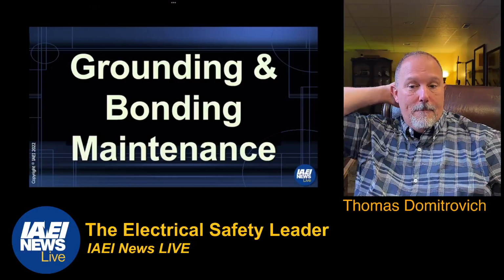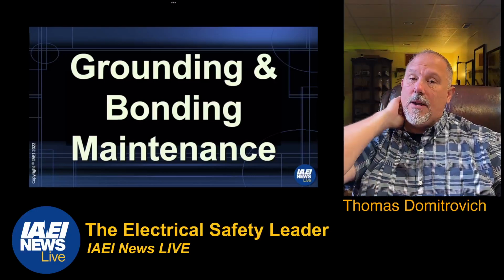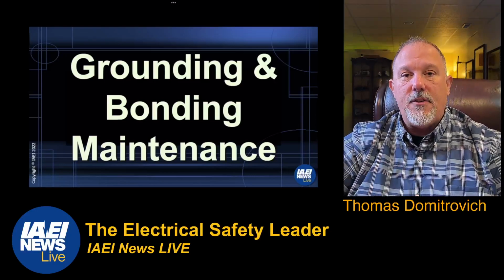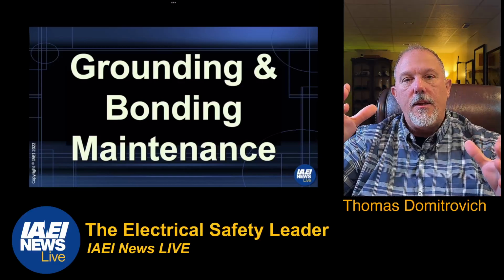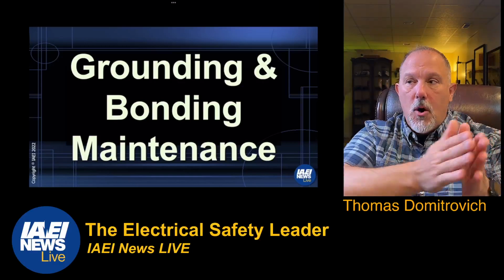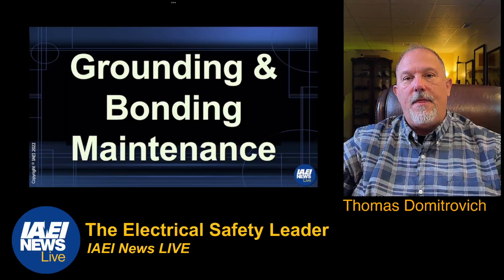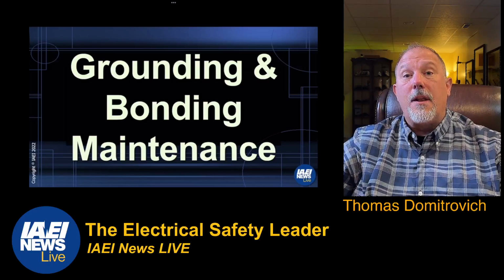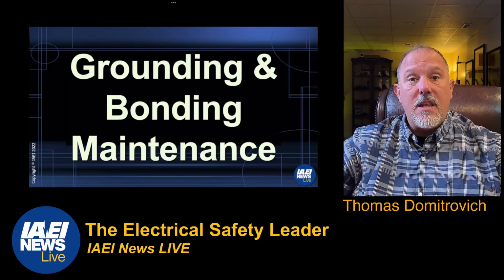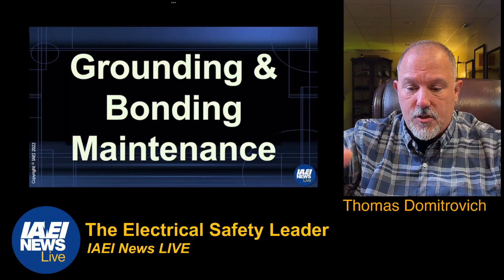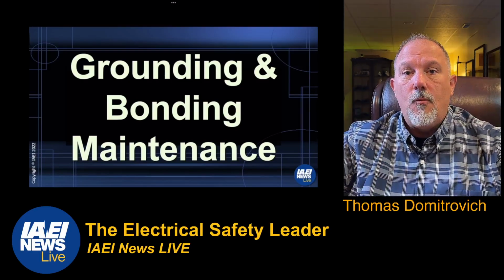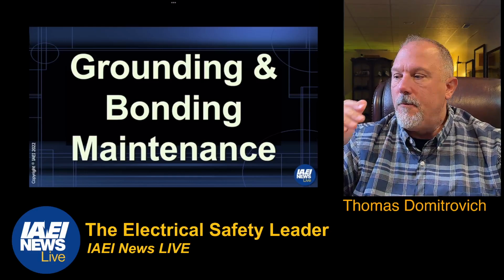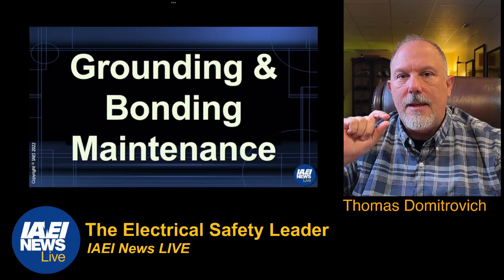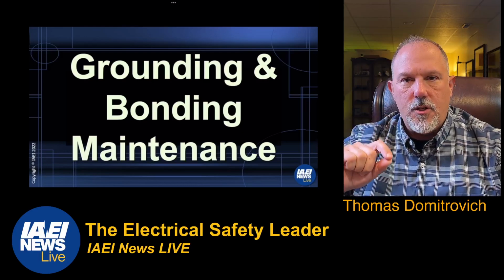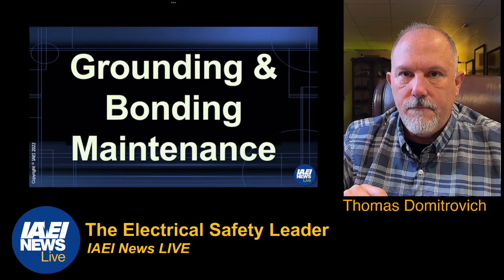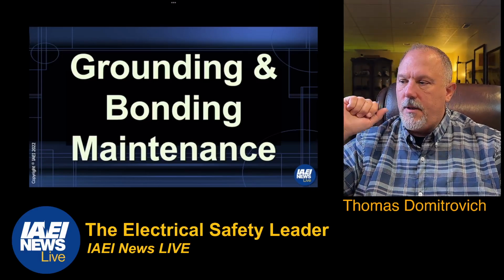As I said, grounding and bonding plays an important role. We want to make sure that when we ground the system and bond all of the equipment together, the integrity of that system is in place over the life of the installation. Many things happen in the process of a power distribution system's life cycle, so we want to make sure that throughout that life cycle, our grounding and bonding system is functional, because when you need it, you need it, and it better be in place.